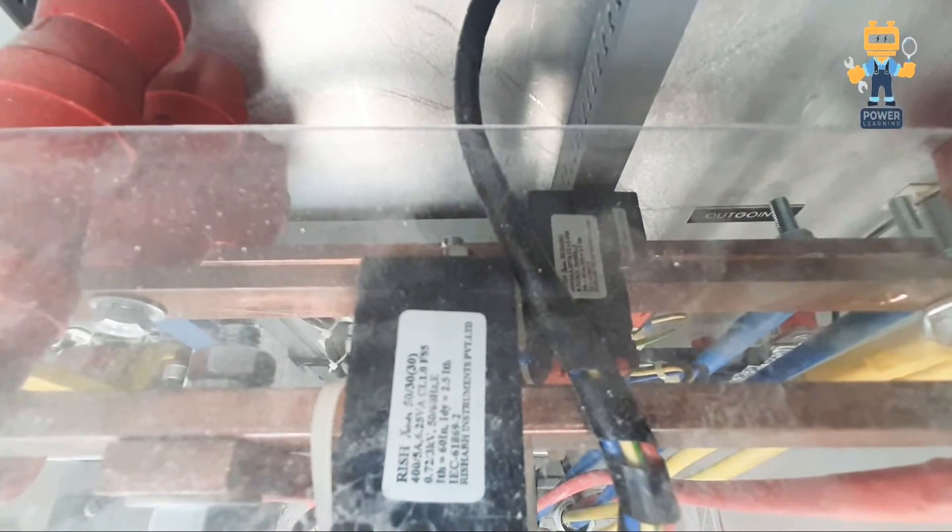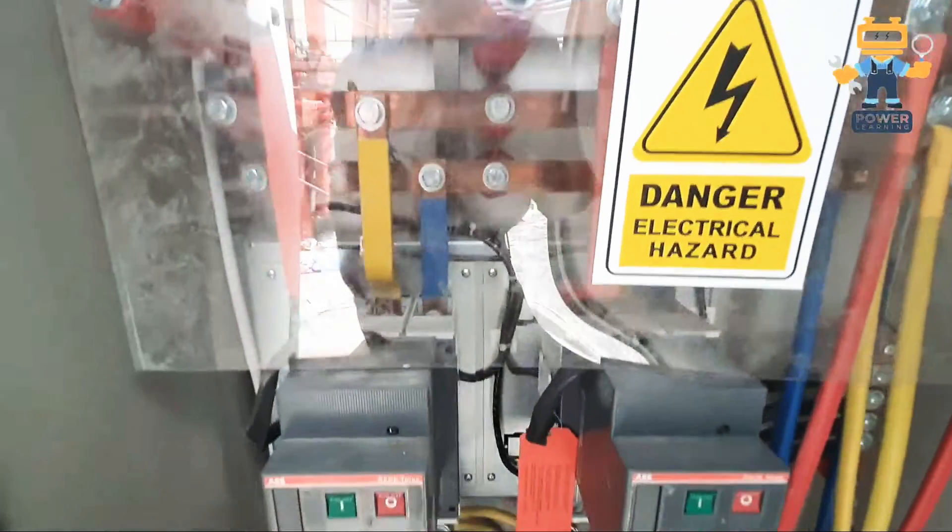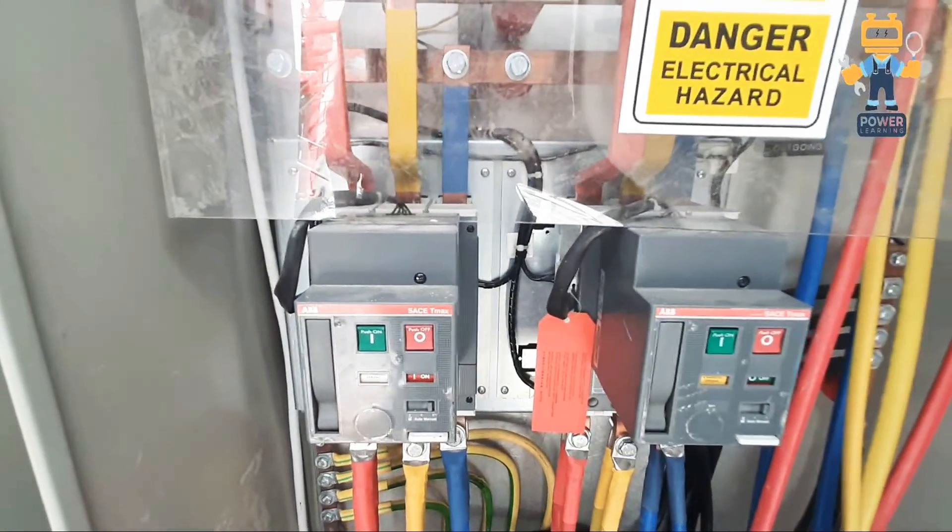Here we have our three CTs. CTs we are using in the panel for current measuring. We are measuring the bus bar current, the load current, with the help of these CTs and giving us readings on our digital multimeter.